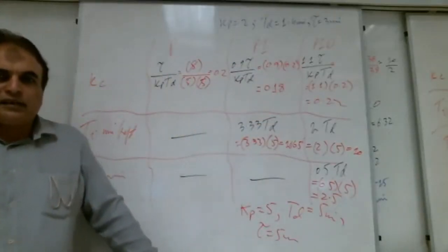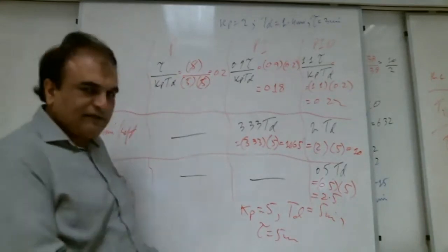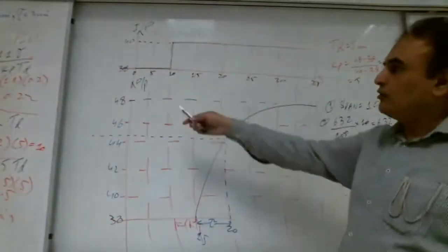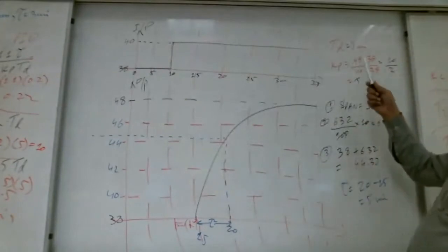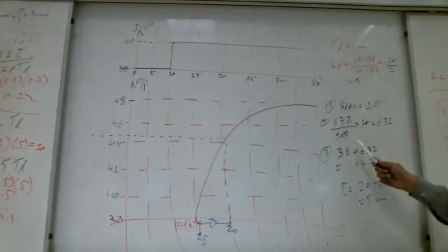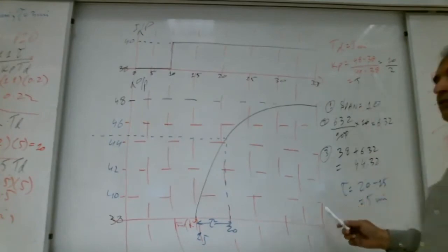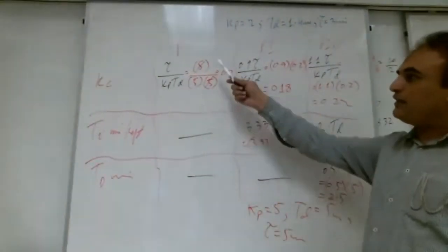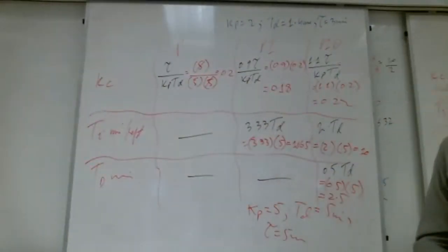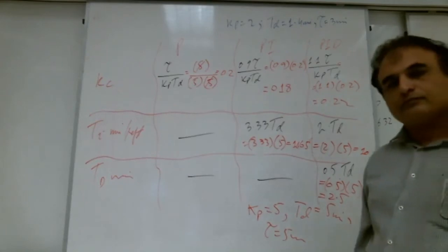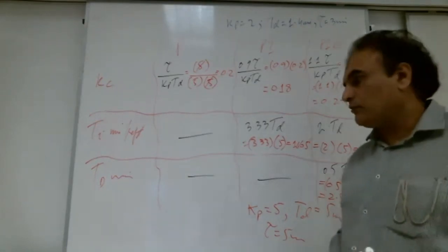So this is the complete procedure. What was given? Input was given, output was given. We found the process gain, process dead time, and process time constant. We bring them into the table and find all the values for the QDR parameters. Shabab, are you with me? That's good. A lot of brothers are saying yes.